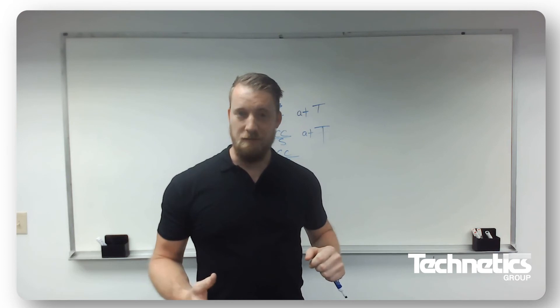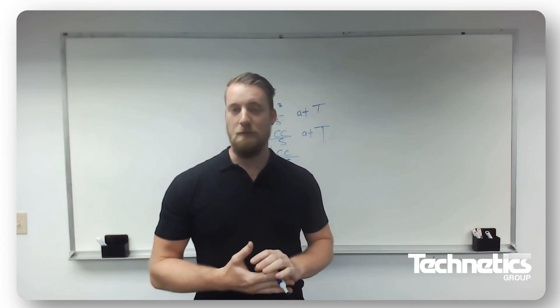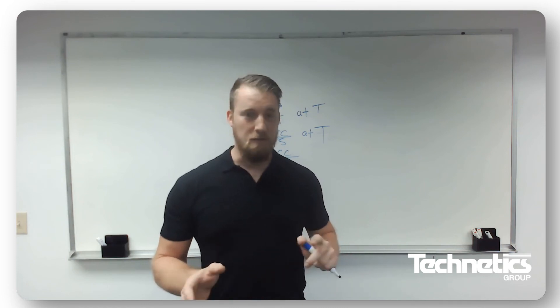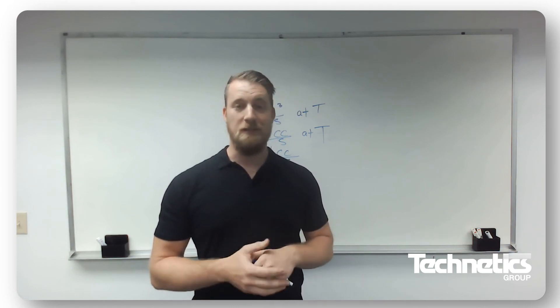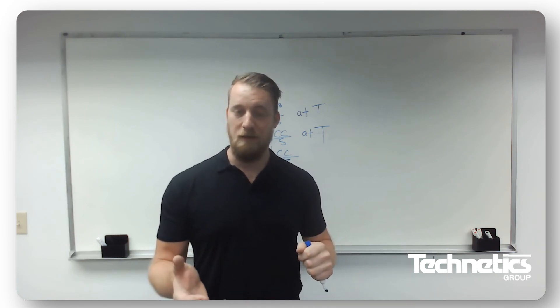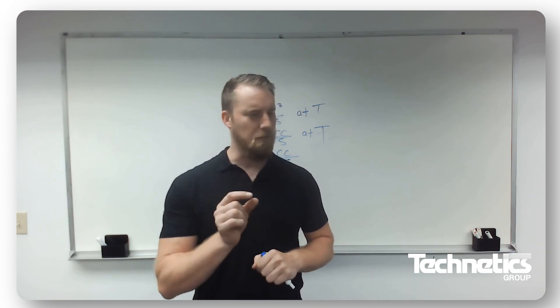And with that system, with that setup, we're able to detect extremely small leak rates down around anything around 1 times 10 to the minus 11 atmosphere cc per second, or even down to 10 to the minus 12. That's a very small leak rate.